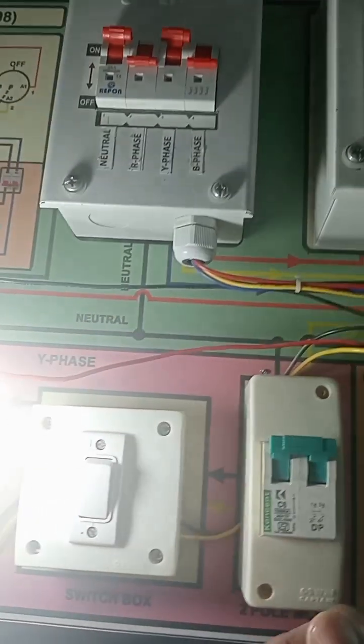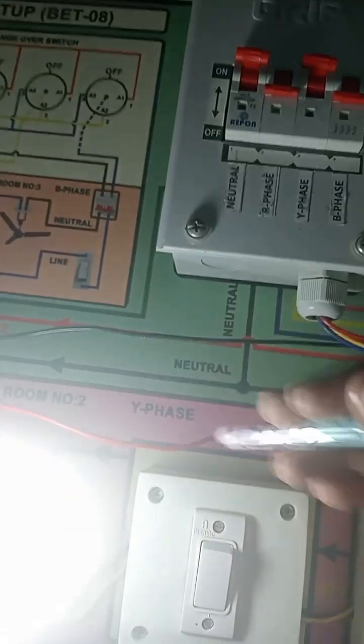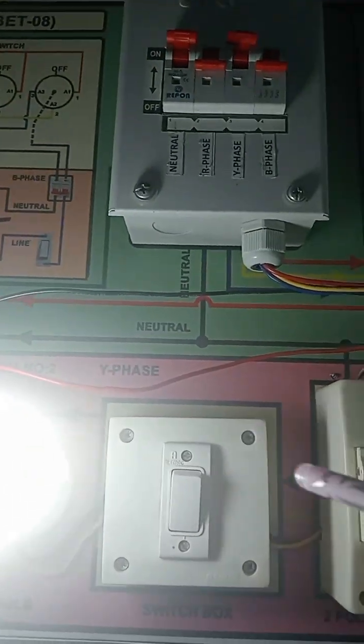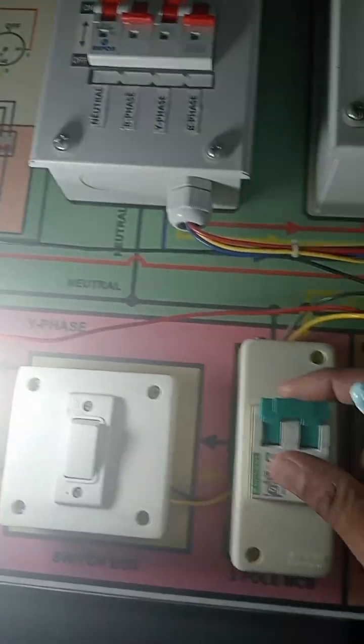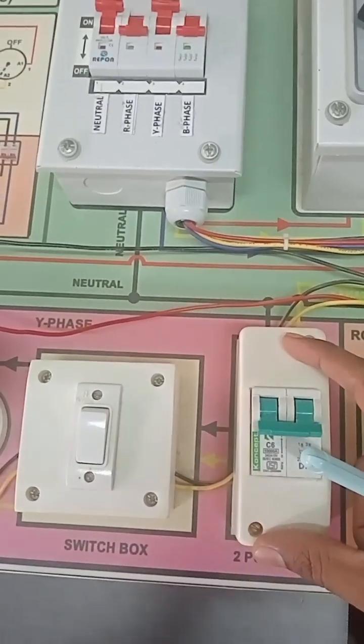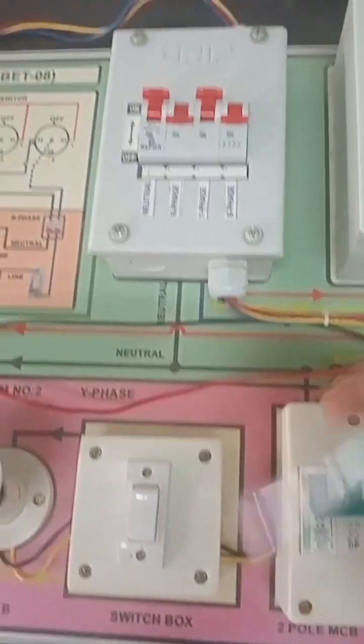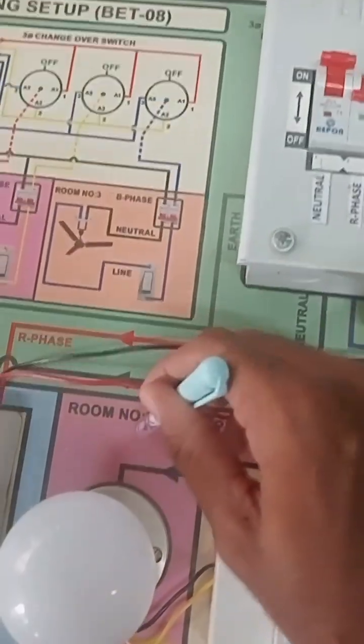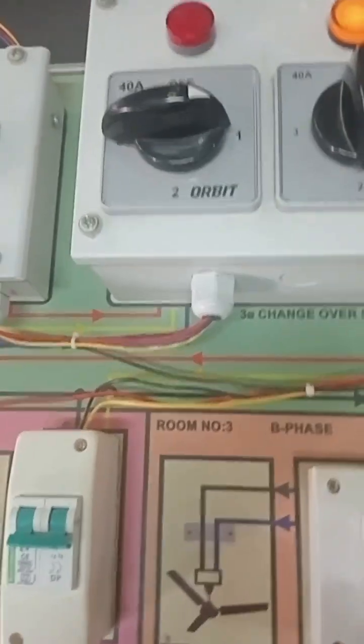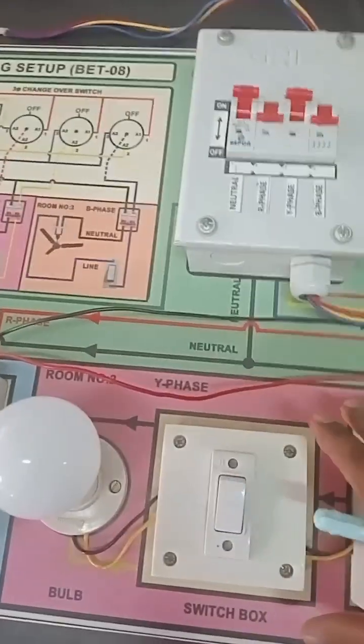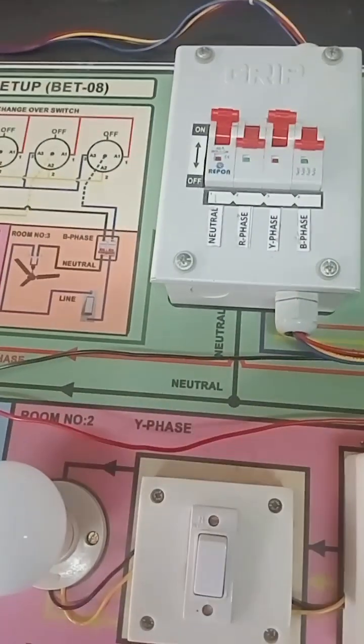You can exclusively go to room 2 and inspect which device is actually faulty. Without this MCB, what would happen is the main MCB would trip off. Then if there is any fault in room 2, room 1 and room 3 would also not receive power supply, because there are no protecting devices for room 2. For individual rooms, there is no protecting device otherwise.